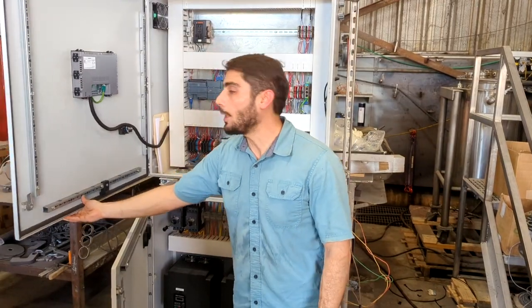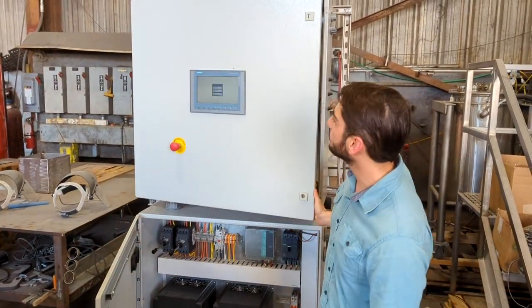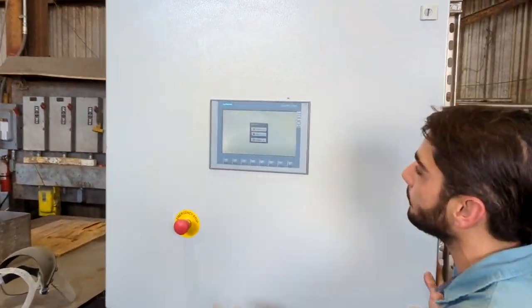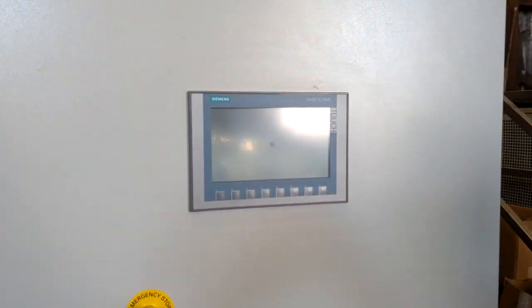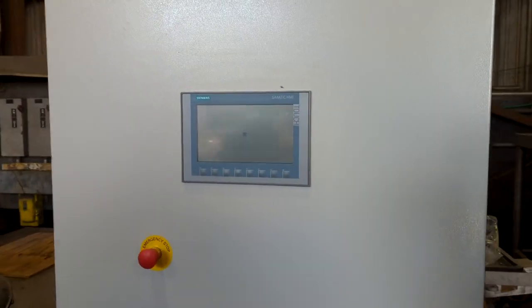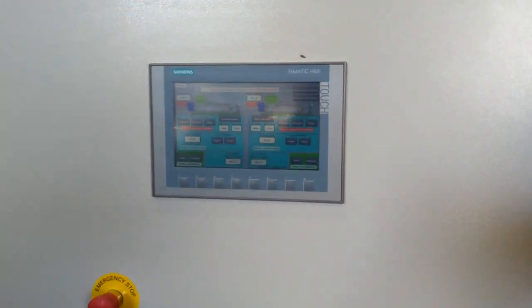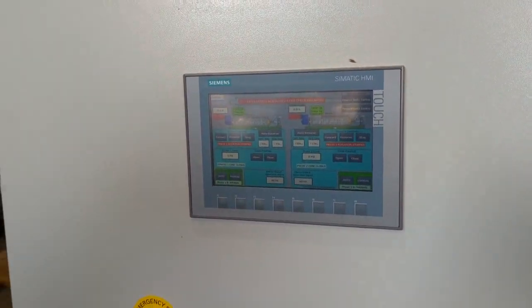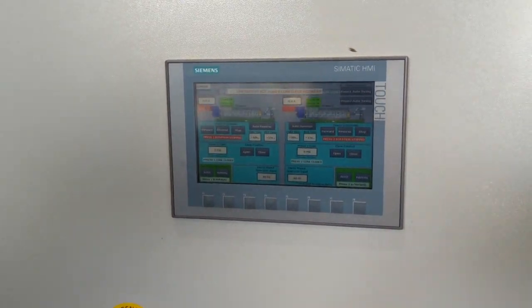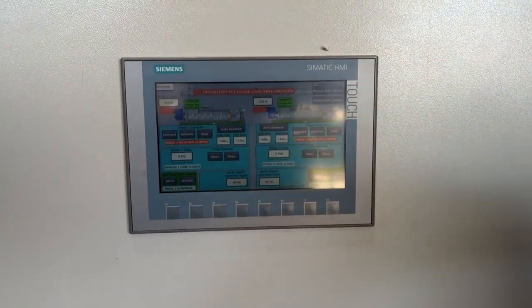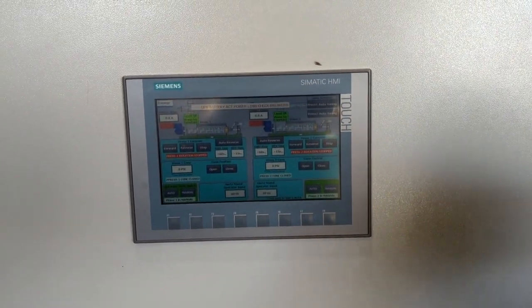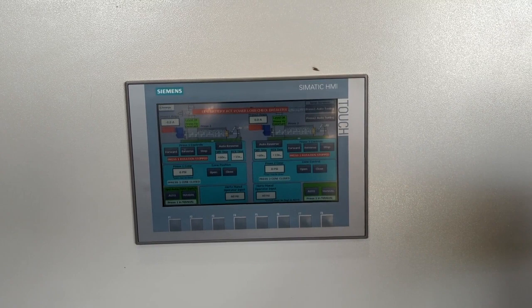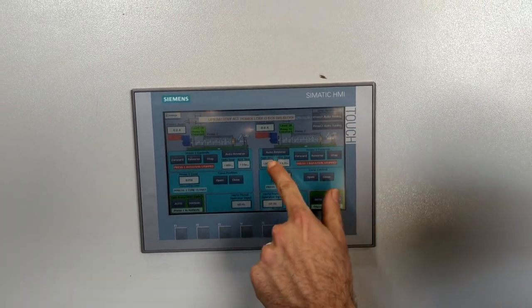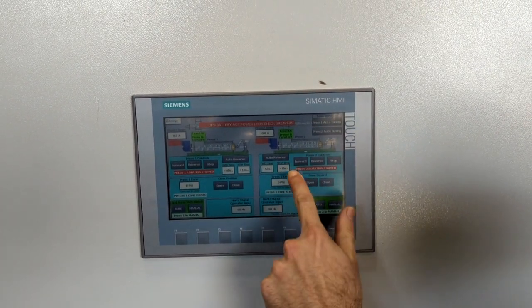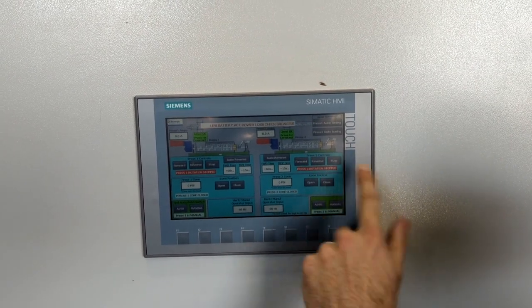So the screen's probably powered up at this point. We can go ahead and run our application. We're doing a few things here. This application is going to be for municipal waste. With municipal waste, we want to make sure that we have an auto reverse feature in there. It'll control how many seconds the press runs forward and how many seconds the press runs backwards to prevent any jamming.